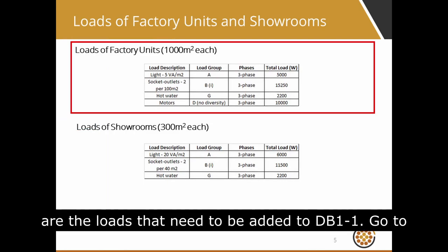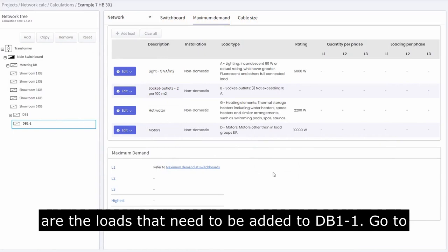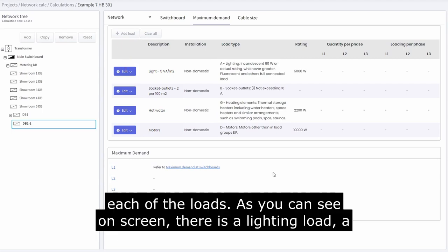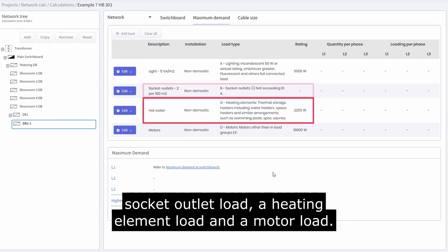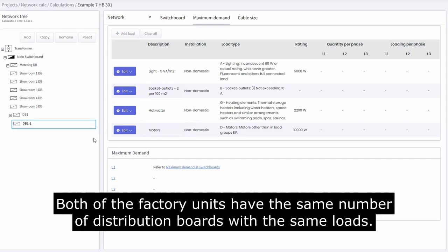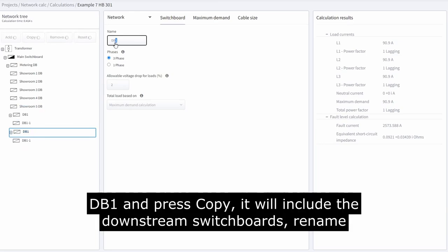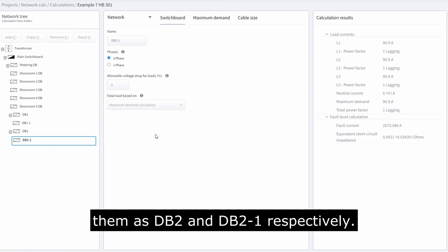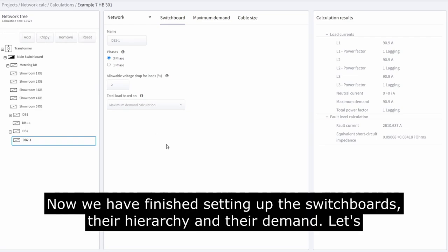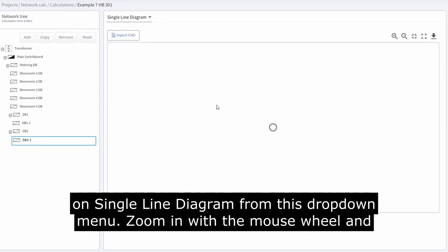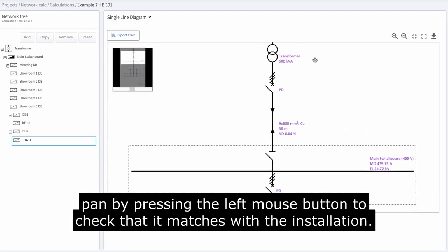The loads that need to be added to DB1-1 are displayed on screen. Go to the maximum demand tab of DB1-1 and click add load to add each load. There is a lighting load, a socket outlet load, a heating element load, and a motor load. Both factory units have the same number of distribution boards with the same loads, so make copies of DB1 and DB1-1 — selecting DB1 and pressing copy will include the downstream switchboards. Rename them as DB2 and DB2-1 respectively. Now that we've finished setting up the switchboards, their hierarchy, and their demand, let's view the single line diagram to verify the setup is correct. Click on single line diagram from the drop-down menu, zoom in with the mouse wheel, and pan by pressing the left mouse button to check it matches the installation.